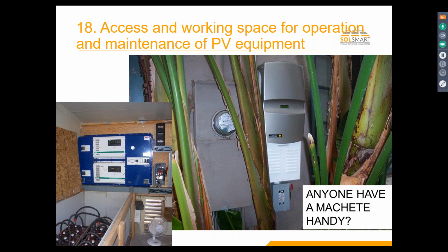So is that fan at the bottom for the ventilation? That appears to be a ventilation fan of some sort. Who knows? Pull the hydrogen gas. That's right. Well, the thing about hydrogen gas, and you know, I'm just going to call that a cooling fan for when you're working on a hot day. Right. Because this vent right here is probably more than adequate for atmospheric ventilation for that room. Hydrogen is exceedingly difficult to contain to toxic levels. And that's because it doesn't go up or down, it just goes everywhere. So you say, well, this is sealed up here.